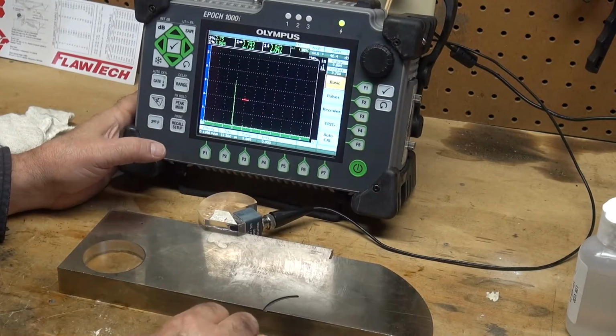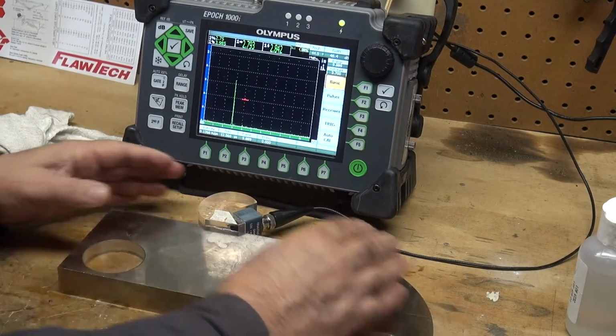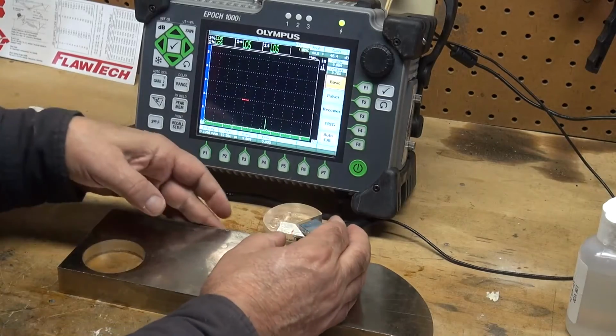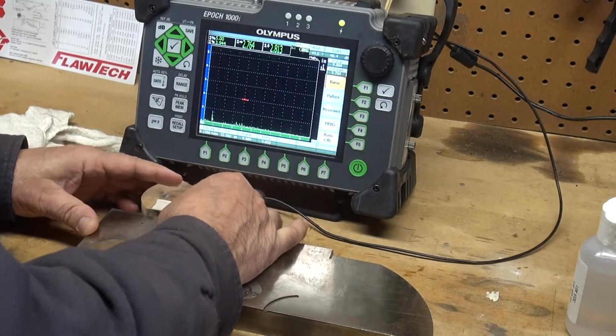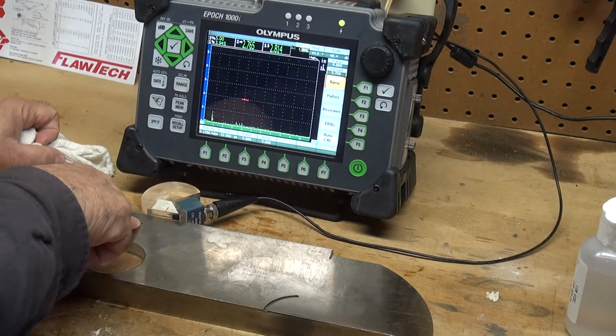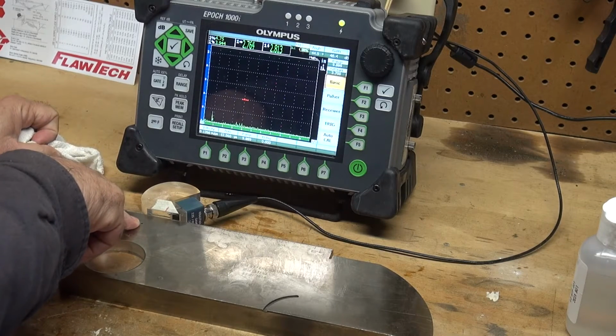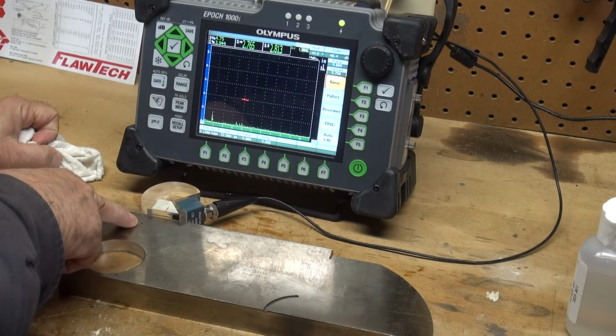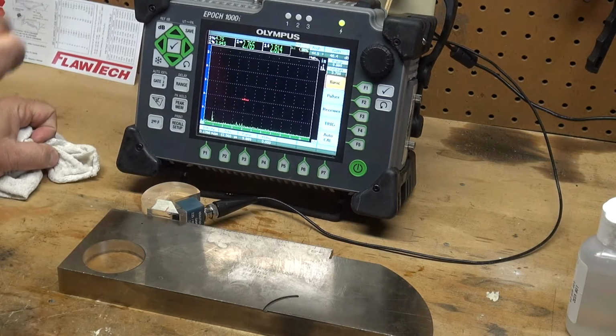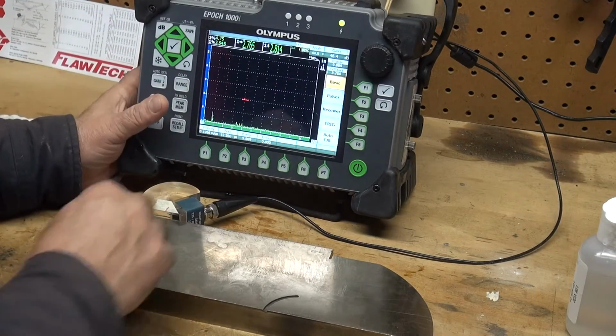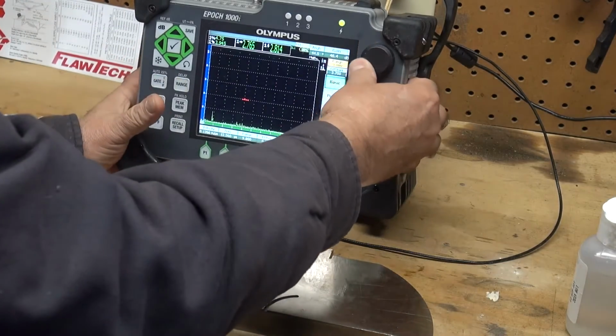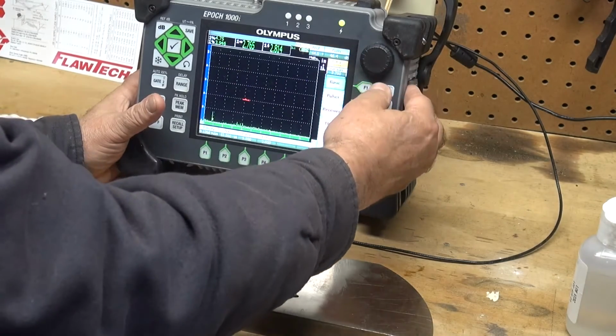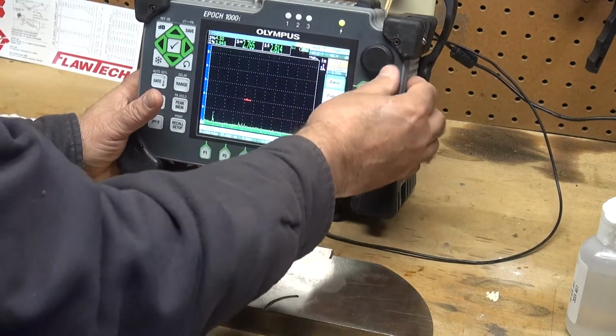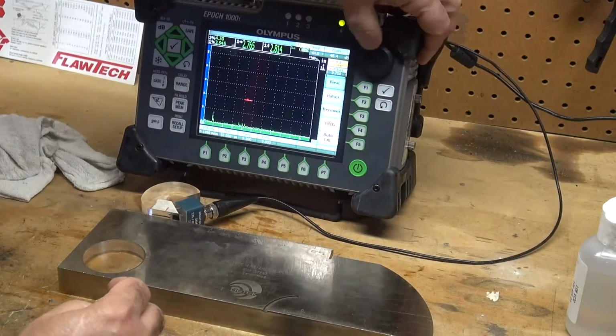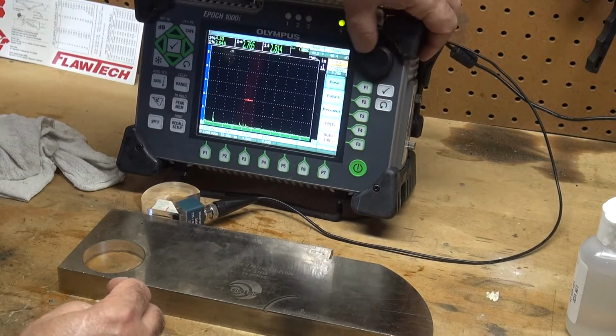The last thing I want to do is show how we set the reference. On the IIW Type 1 block, we have a 60 thousandths diameter through hole that is 0.6 inches below the surface. That is used to set our reference sensitivity. Now, let me change my range down to 2 inches, because 10 inches is far too much. And she is going very slow today.